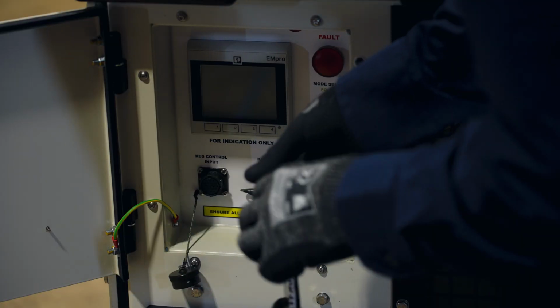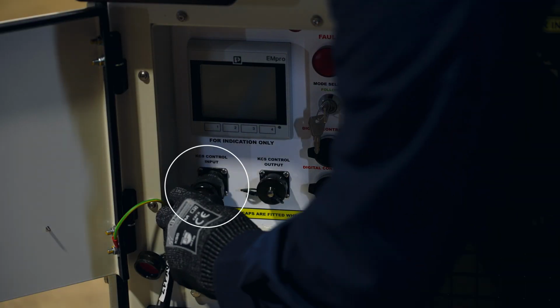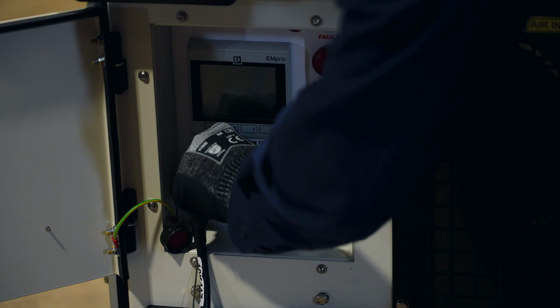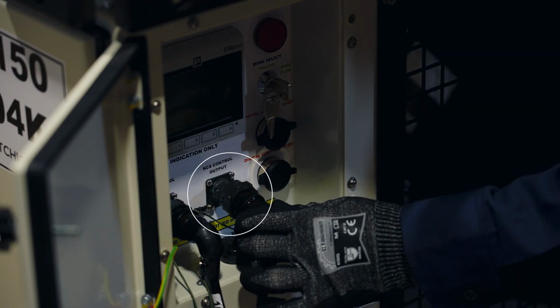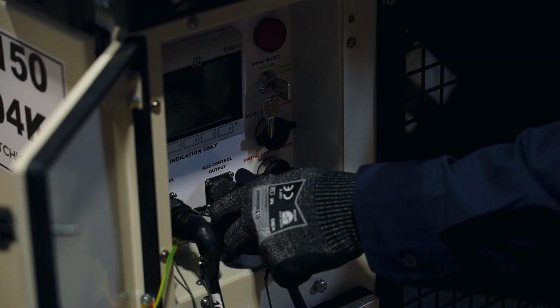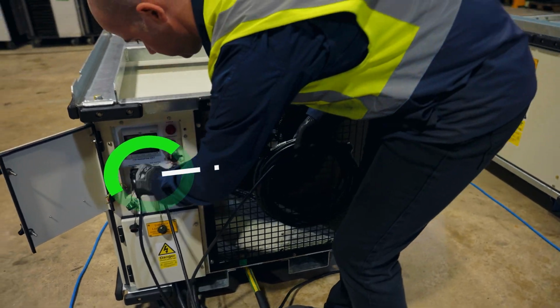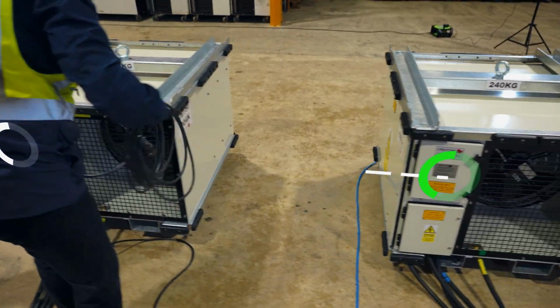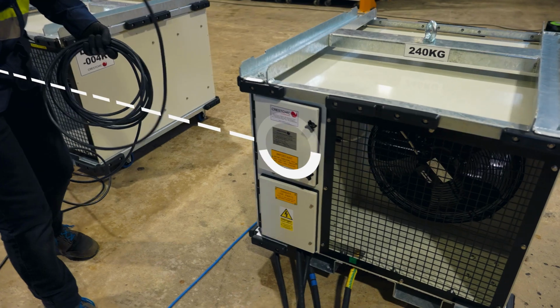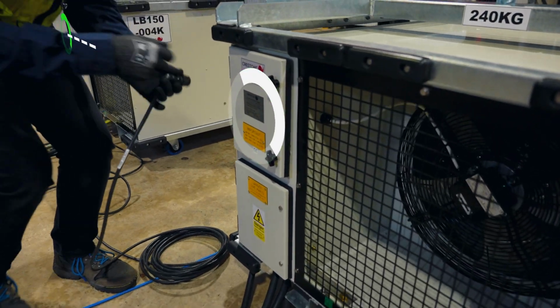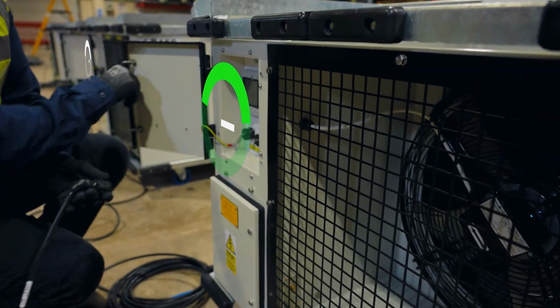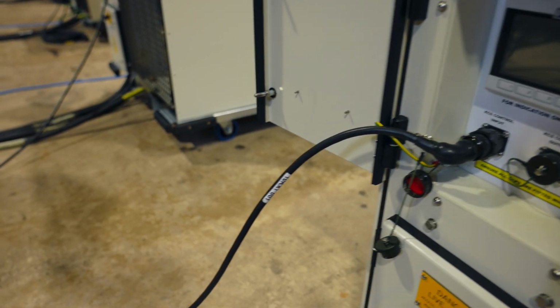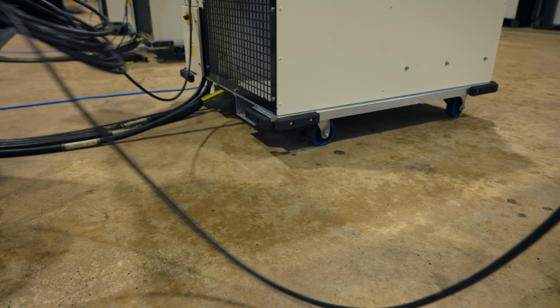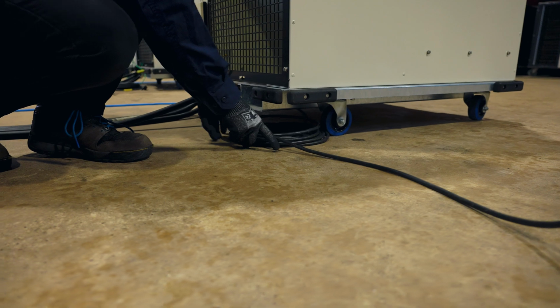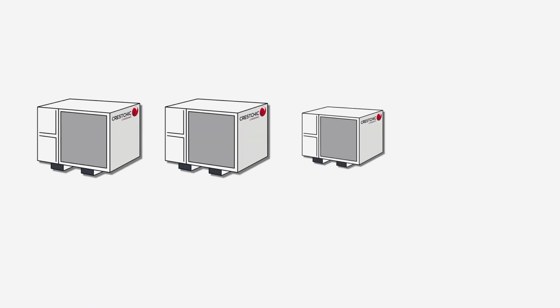In this demonstration, we are showing the load banks being connected together and controlled from one controller. Simply, the controller is connected into the control input of the first load bank, then a control cable connected from the control output of this load bank into the control input of the next load bank, and this is then repeated on the rest of the load banks until they are all connected. The control cables and the controller should be placed away from load cables and the hot exhaust heat from the load banks. The load banks can be loaded in two different methods.